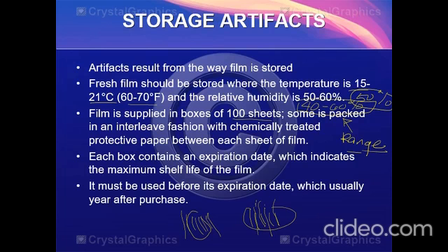Usually, the shelf life of the film is about 1 year. Pero pwede siyang ma-extend, provided that we observe the proper storage protocols for long-term storage of the film. Hindi naman siya agad-agad nag-expire ng 1 year. Kaya lang, hindi na ganun kaganda yung quality ng ating images sa radiograph pag lampas ng 1 year.